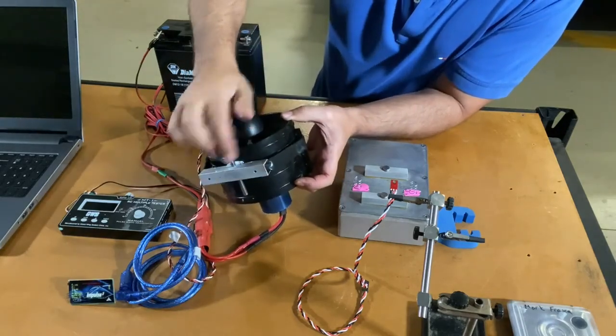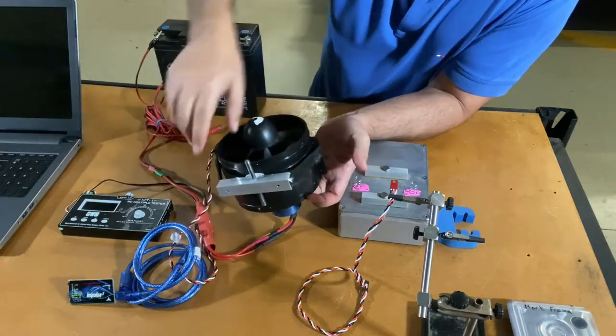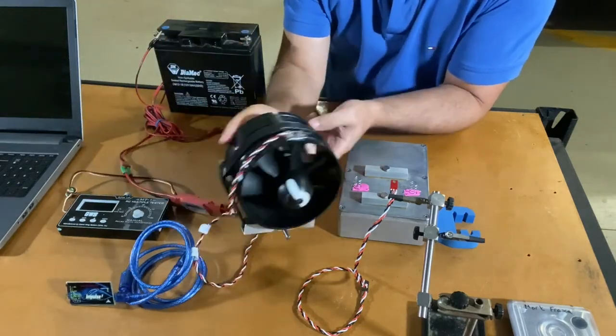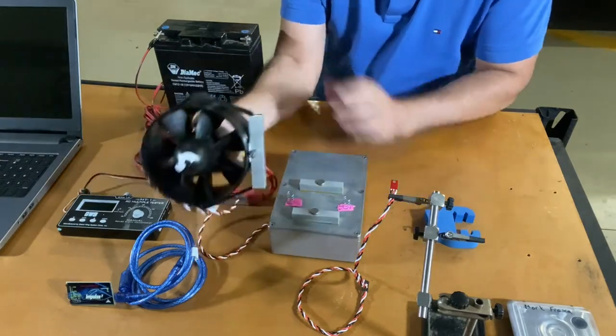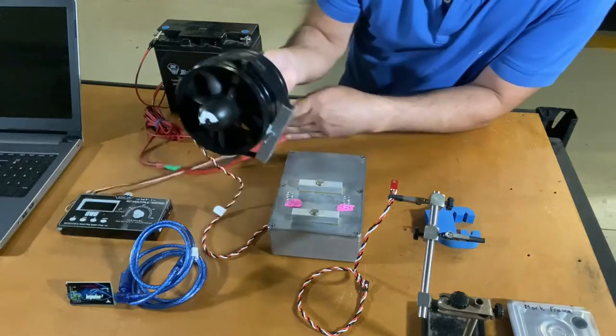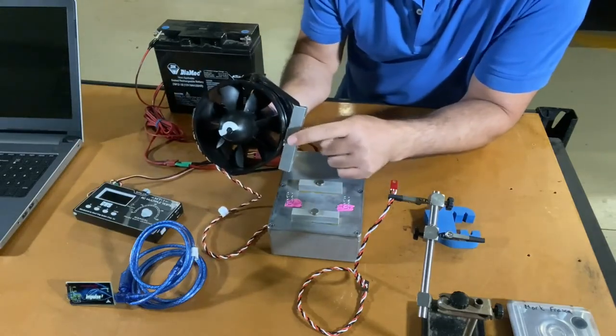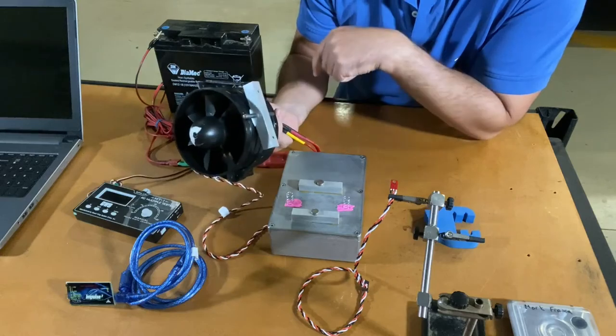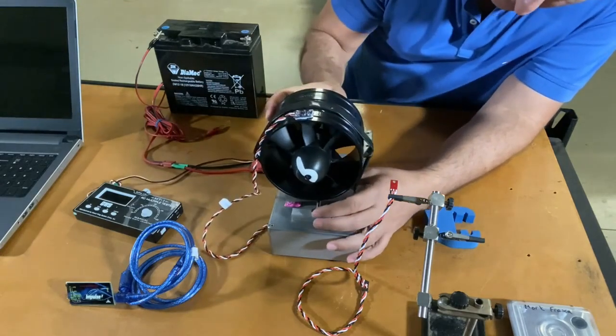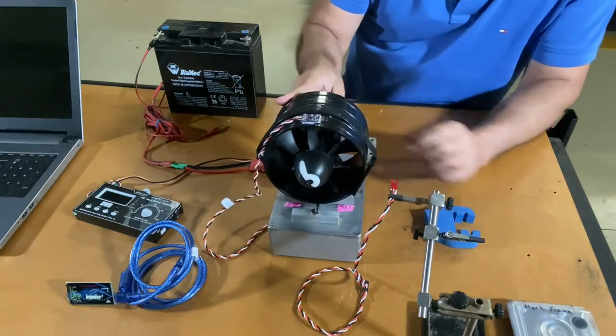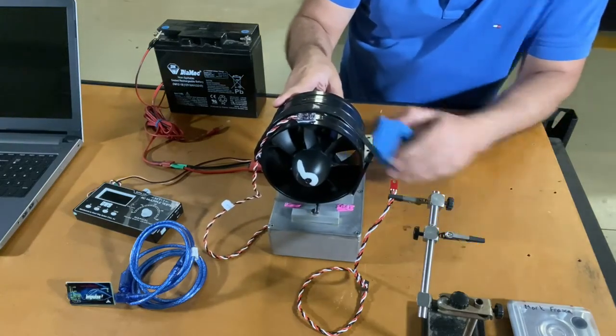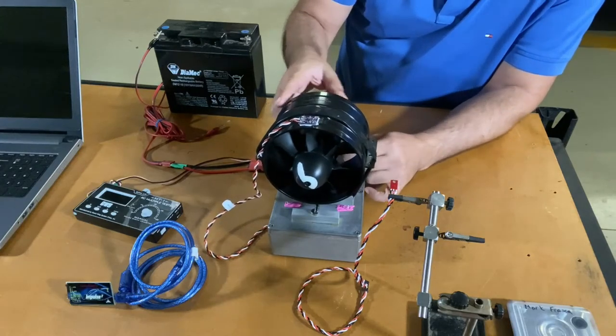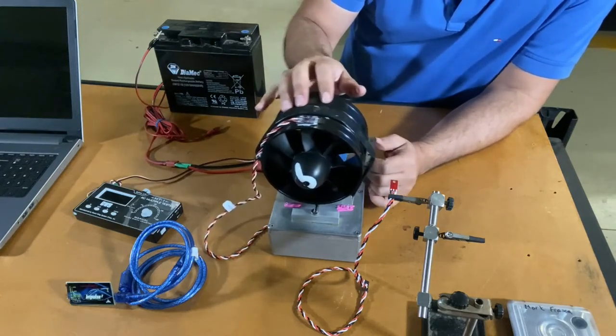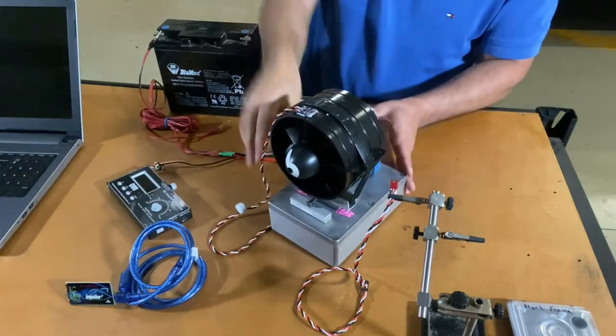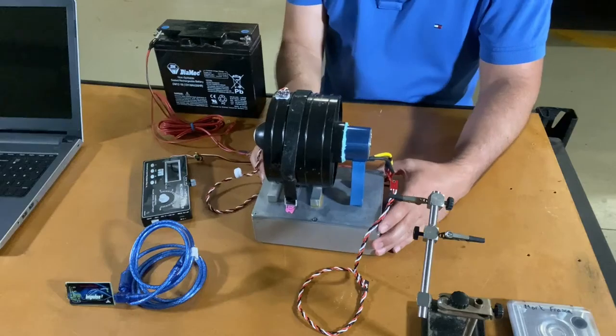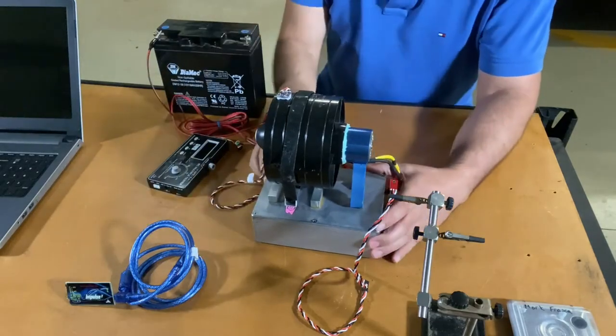Now that sway bar is actually attached by a Velcro strap all the way around the EDF unit. Now when you actually position the EDF onto the base, the rare earth magnets will actually snap onto the steel bar. So when you attach it, it'll form a nice sort of pivot mount like that. And the good thing about this is it allows the EDF to move in its natural state when it's vibrating. So I'm just going to rotate the base so you can see the side profile of the mount. There we go.